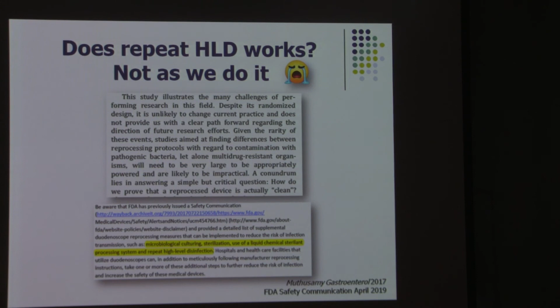At this point, we are following the FDA's previously issued safety communication. The most recent one is from April of 2019, and it still recommends using one of those 4 measures, including repeat high-level disinfection. So until, the way I see it, something is different, that is what we need to follow. Now, the next step is: how do we know that with all that effort we're actually doing a good job? These interesting studies, or summary of interesting studies, were actually using a borescope, a small scope that goes inside the duodenoscope channel, and kind of asks and answers the question: what do we find there?